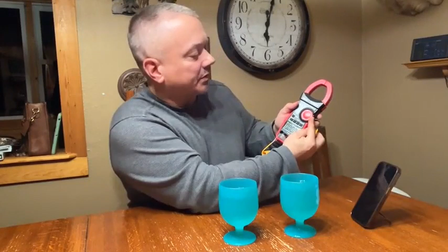Another feature is the temperature probe. This is going to measure temperature. I'm going to install those right in there and move this over to the temperature setting. Right now it's reading the air temperature, and you can watch what happens when I submerge the probe into cold water - you can see that the temperature drops down relatively quickly. And with the probe into warm water, the temperature goes back up very quickly.